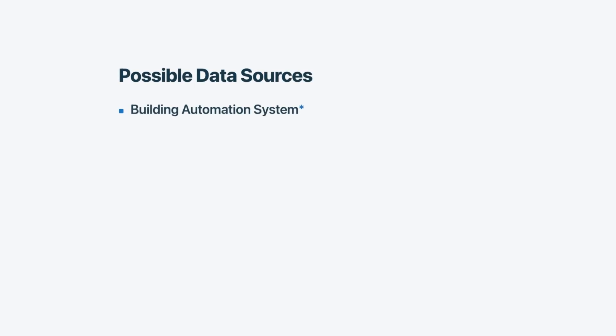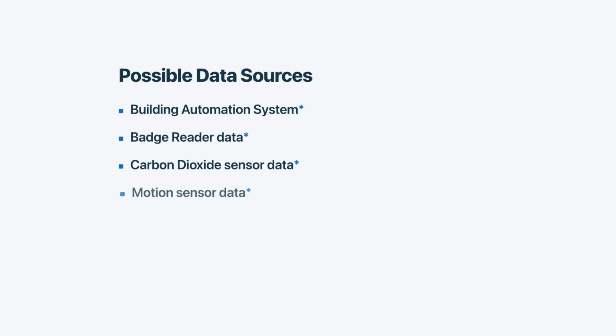But here's the catch. Fixing a schedule without real data is just guessing. People tend to guess in the direction of caution, keeping schedules longer than needed to avoid complaints. But the data you need isn't complicated. You just need a couple of key pieces of information. If your building doesn't have a badge reader, you can look at things like the carbon dioxide level rising to estimate occupancy patterns, or motion sensors.